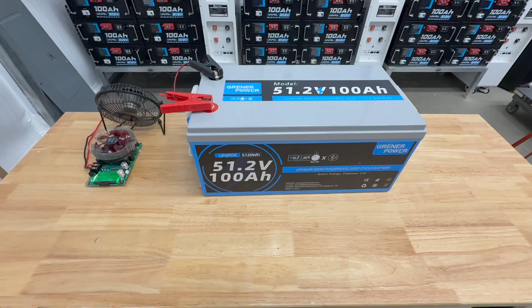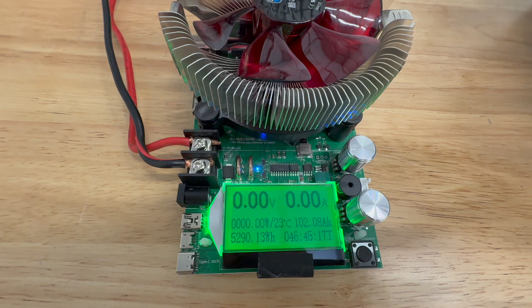All right, so the capacity test is finally done on this Greener Power 51.2 volt, 100 amp hour battery. We got 102 amp hours out of it - it's rated for 100, so we have 102.08 amp hours and 5290 watt hours. It ran for 46 hours, so we did a slow discharge on it. Not too bad - it does actually put out more than the rated capacity. I've seen some 100 amp hour batteries put out 104, 105. This one did 102, which is fine.